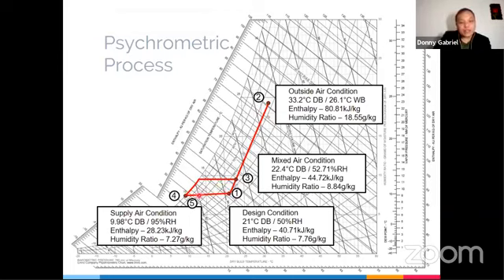Previously, we already determined this line, 90% sensible factor. Remember, parallel lines from our protractor. Okay. Now, this line, all right, when 2 points or when 2 conditions of air mix together, from our instance, the outdoor air and the return air mix together, the resulting condition will fall within this line.